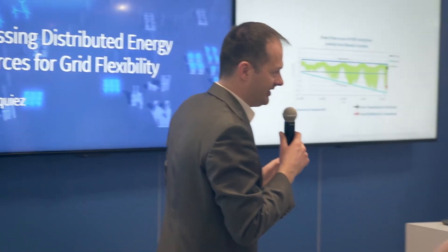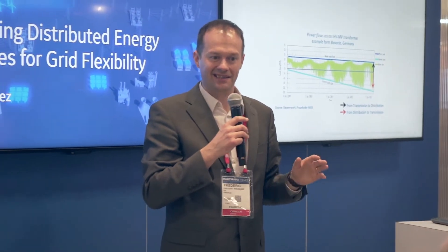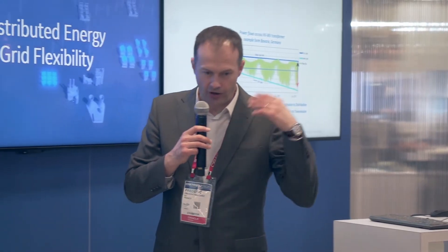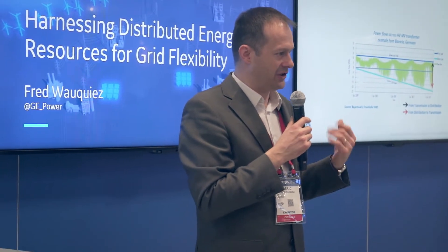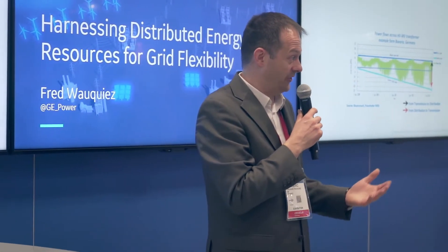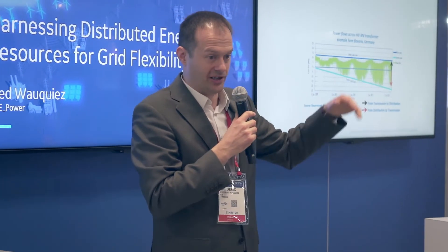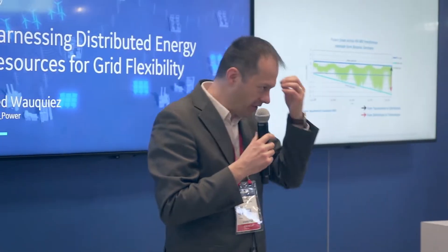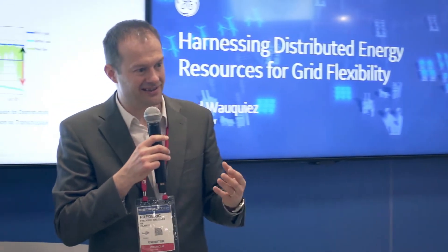Maybe you're not there yet as a utility — there isn't that much PV on your grid today. You're not Bavaria, you're not California yet. But this will come, so you'd better prepare. Preparing means knowing what happens and understanding all the processes and logic attached to it. You're used to running your grid knowing that voltage drops — but no longer. When there's PV, there's a voltage rise. So you have a voltage profile that is just not the regular pattern, and in all your daily operator routines, you need to think differently.